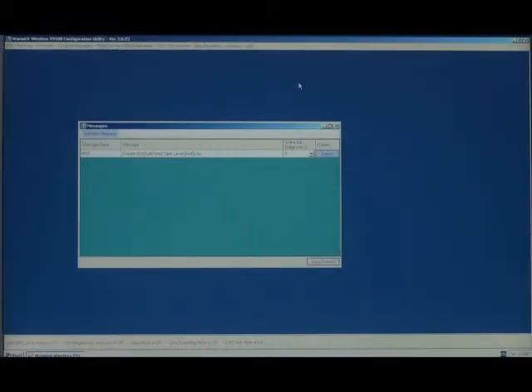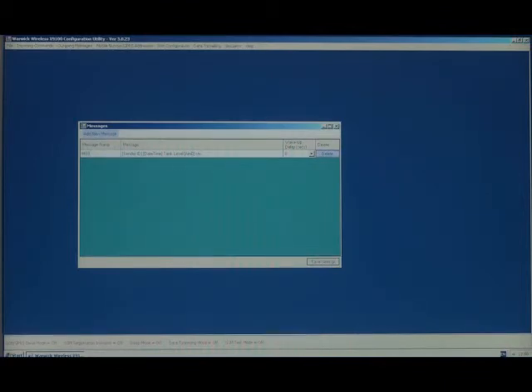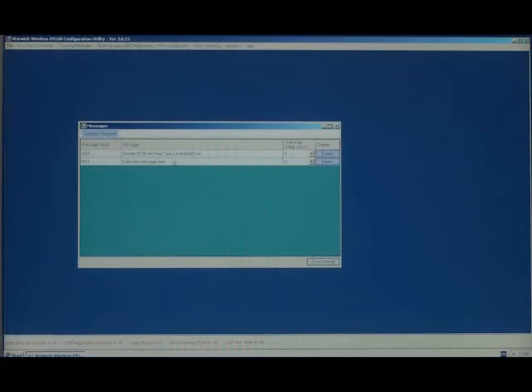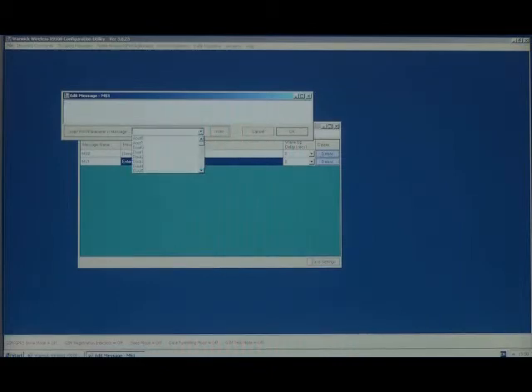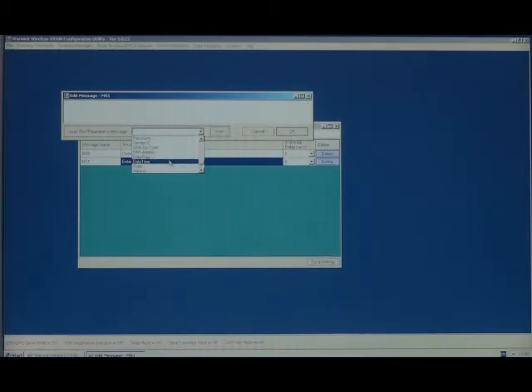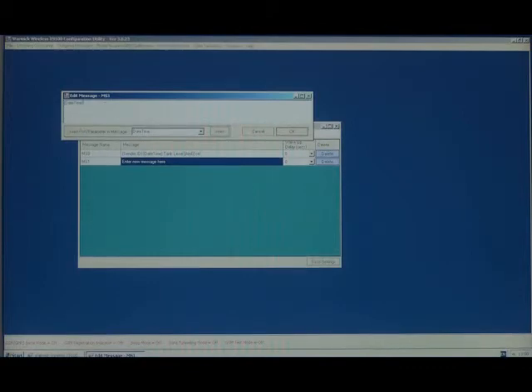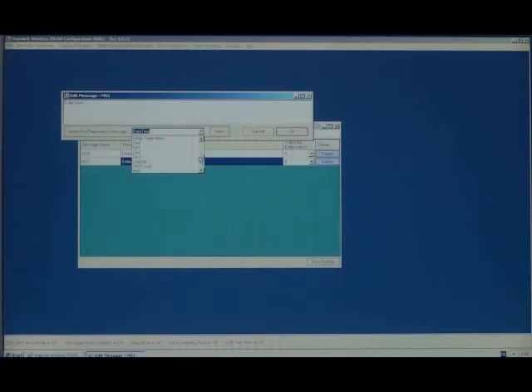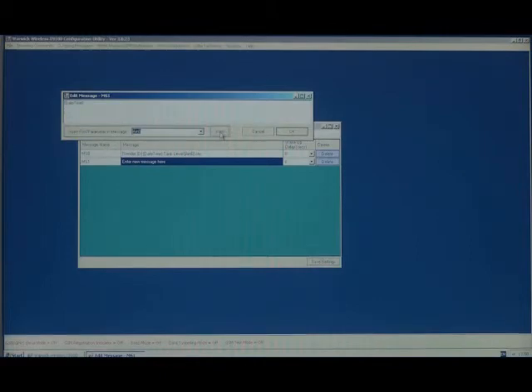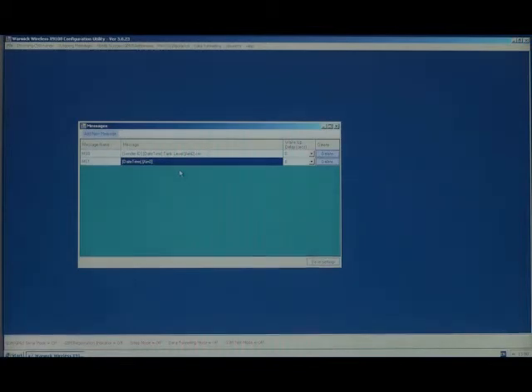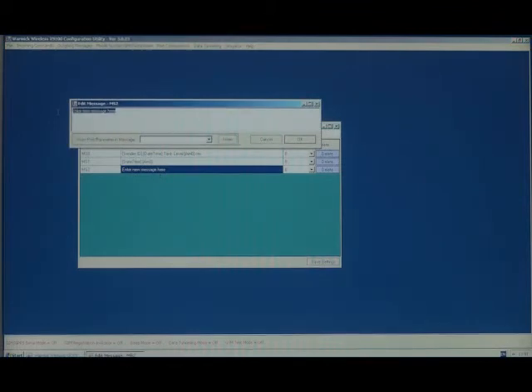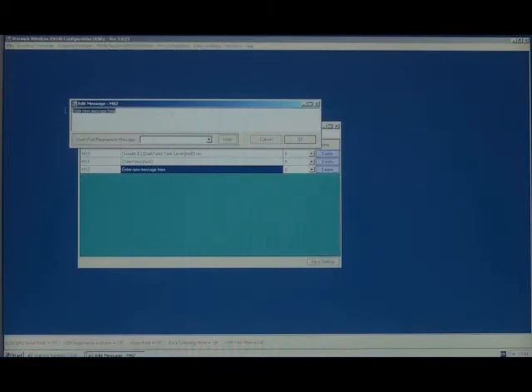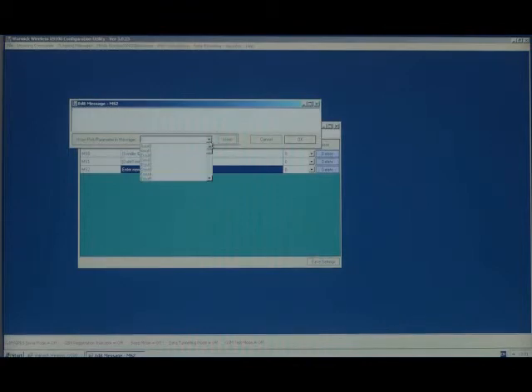It might be that we want to log the results of the tank and send it to the website once a day. For this, we would enter a new message, which would be the value of the tank and the time it was taken. So we would use the date time stamp and the value of the analog input, which would be AIN0. We would OK that. And we'd have to compose a new message, which will send the contents of the log to the website, which would be simply the parameter log.